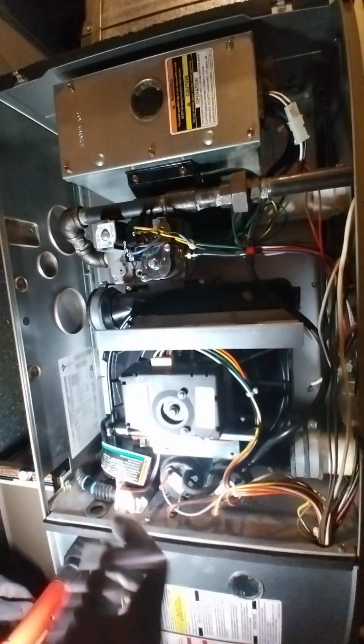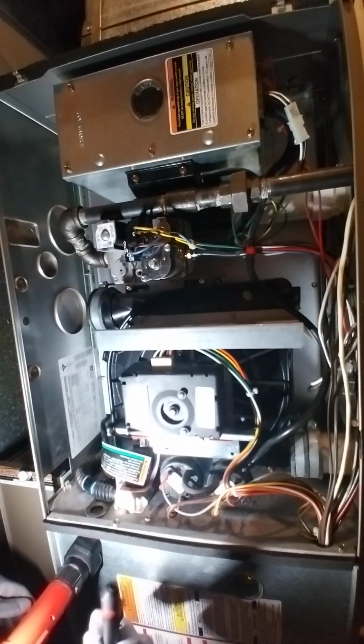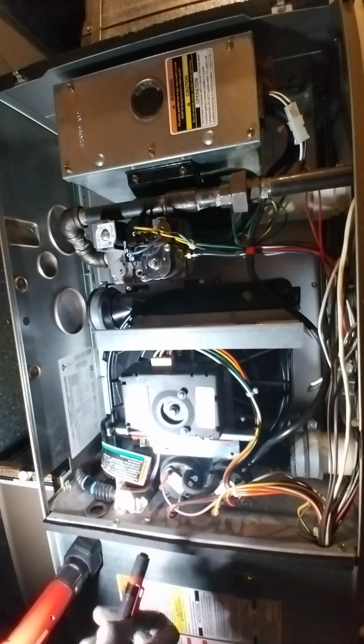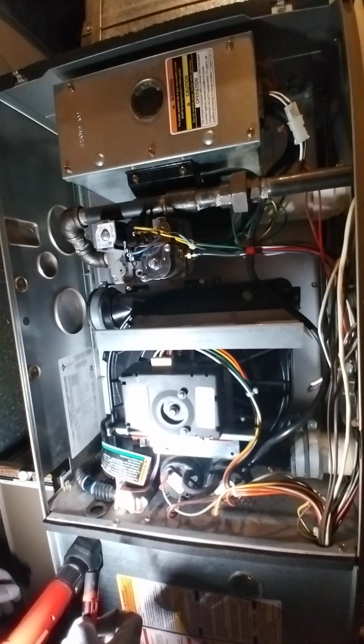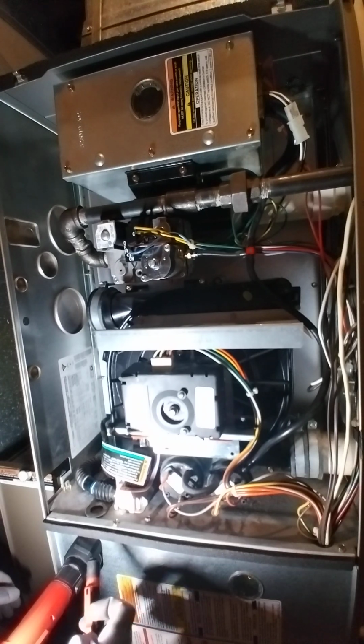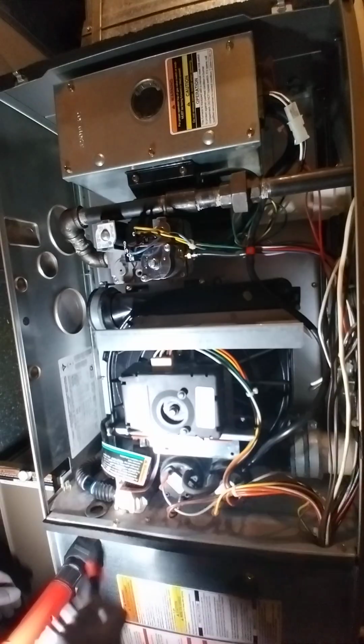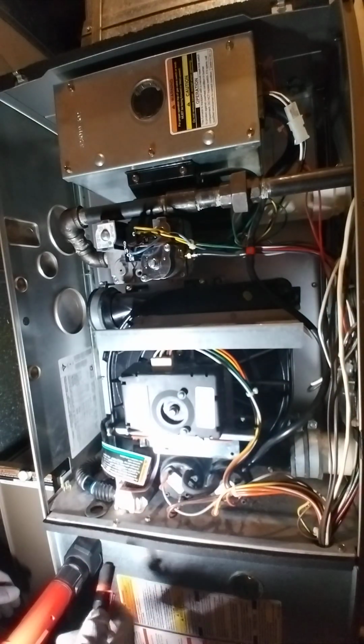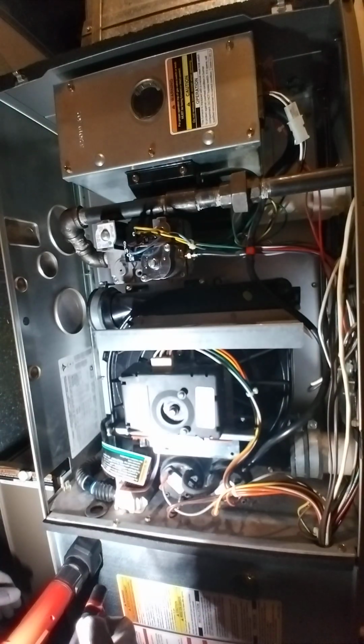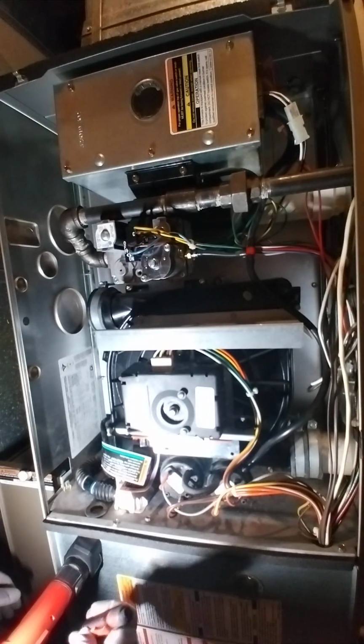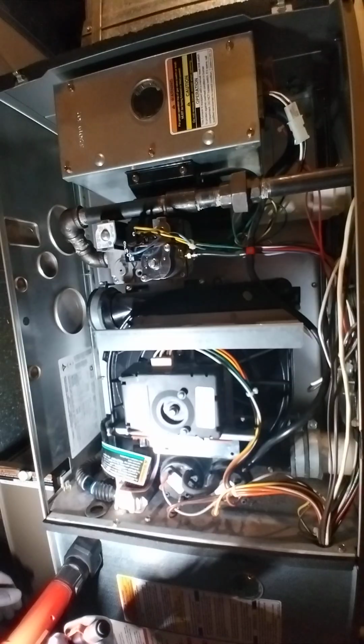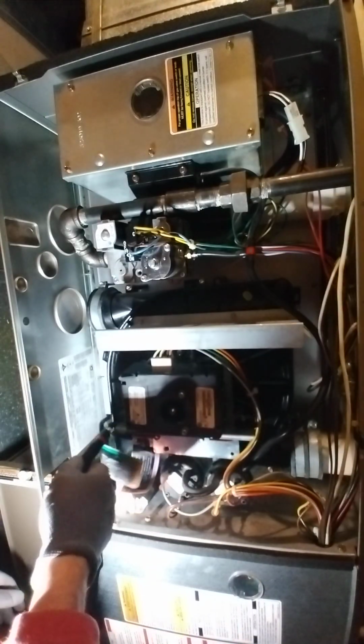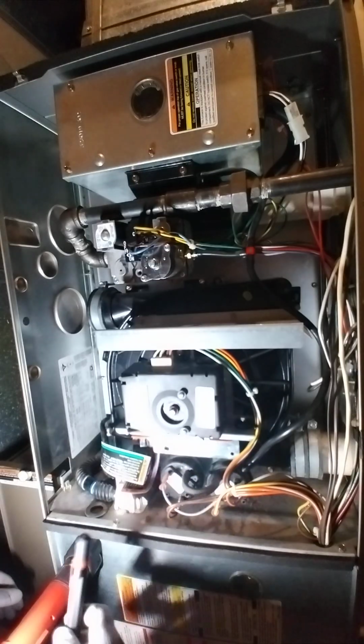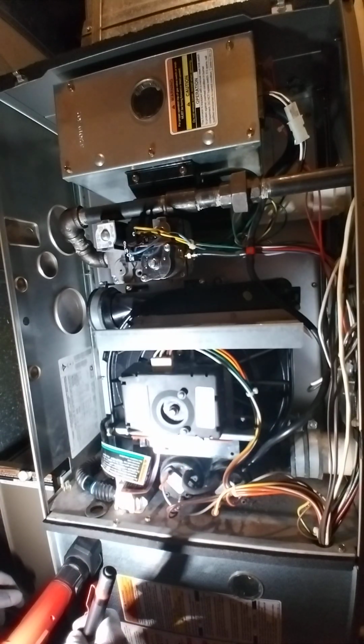But one thing I noticed when I was Googling and trying to find out why furnaces short cycle, this particular issue I didn't find. I'm sure it's out there in a forum somewhere, or a random post or something like that. But you don't typically go past the first or second page of Google results. And I never saw this as a particular problem. In fact, the maintenance manual doesn't even list this as a possible cause for the furnace to be flashing the error codes that it did in diagnostic mode. It said that this could possibly be clogged, and or one of the little air tubes here could be clogged, but it never said that it being empty could be a root cause of this particular problem.